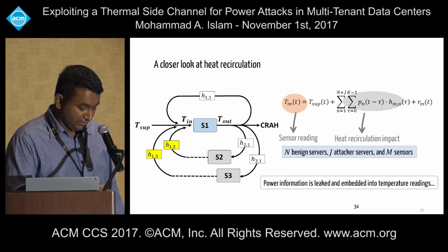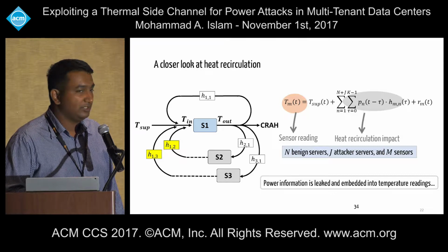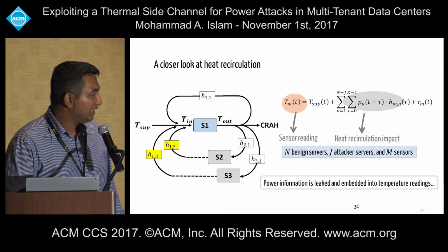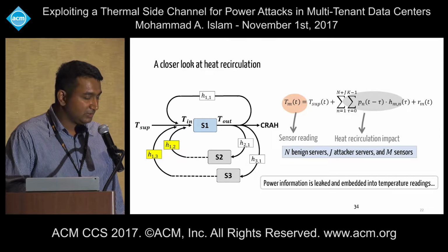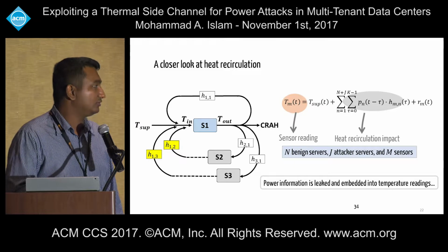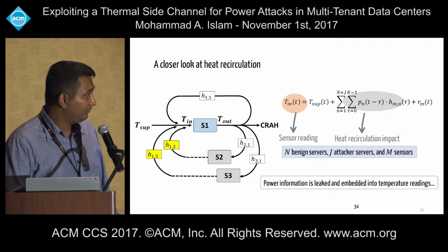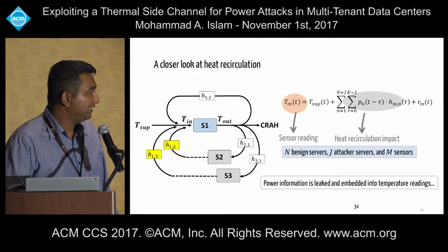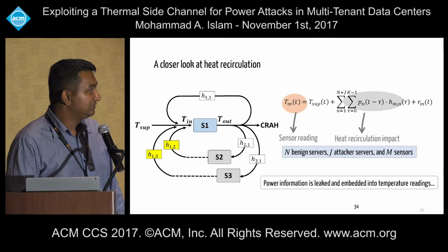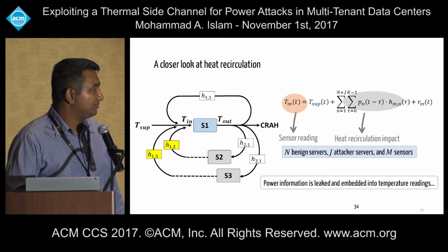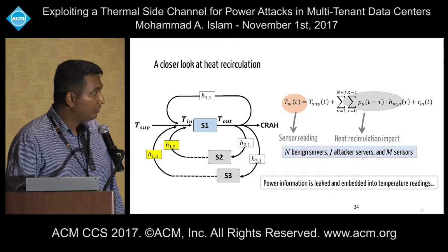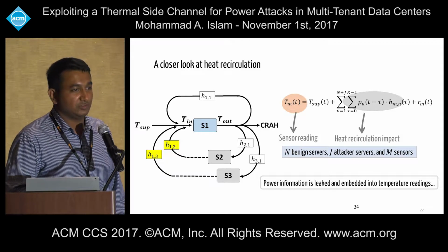Due to heat recirculation, the exhaust heat from server 1 comes back to S2 and S3, as well as its own inlet. Similarly, heat from servers S2 and S3 also goes into server 1. So if we put a temperature sensor at the inlet of server 1, what we see is the supply temperature plus the impact from other tenants' power consumption.